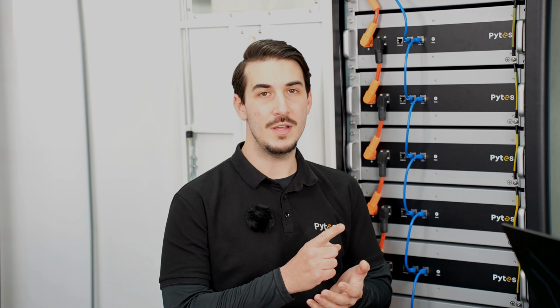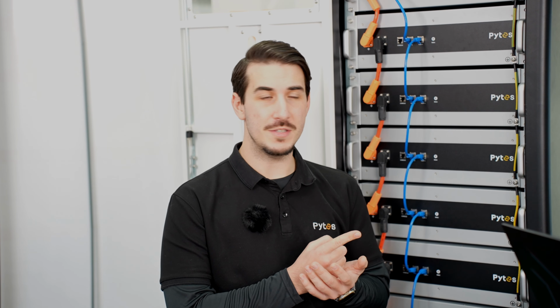So it really does simplify the design and overall makes things a lot more efficient. If you compare a system with one large inverter versus 3 smaller inverters, you're usually saving a lot in terms of not just the inverter cost, but also your supporting accessories—less cable, less conduit, less components overall to get the same end result.